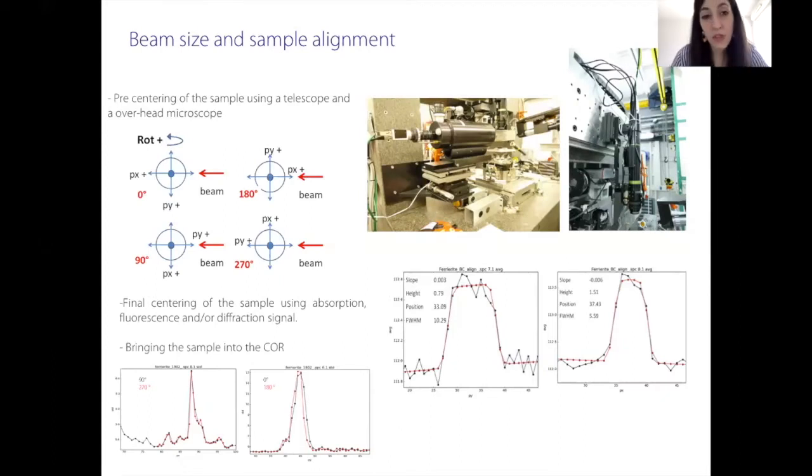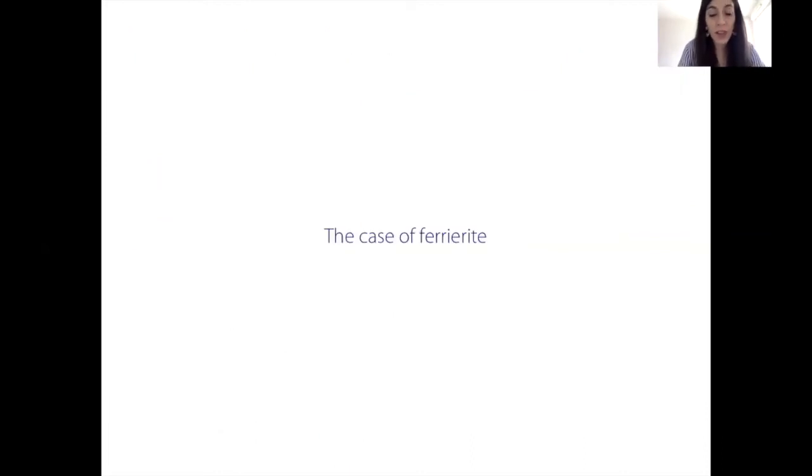Before performing any single crystal or diffraction experiment, we want to be sure our sample is well aligned in the beam. For this reason we use a telescope or overhead microscope and perform final centering of the sample after having optically aligned it by using the absorption signal, fluorescence, or diffraction signal. Of course we want to be sure the sample is in the center of rotation.